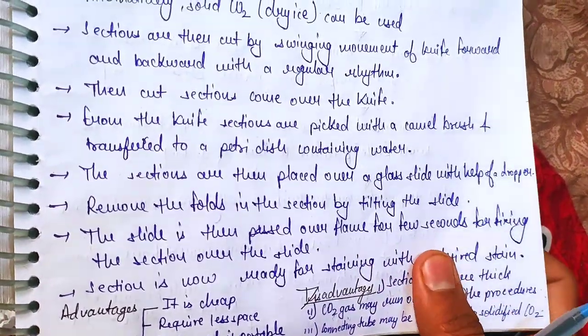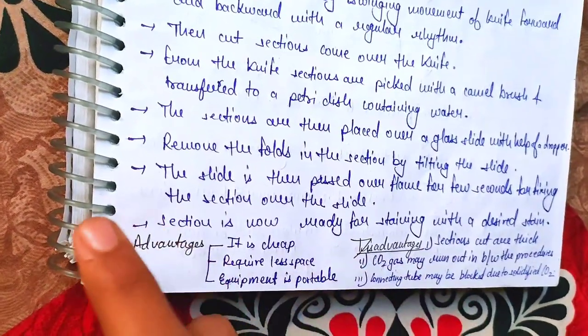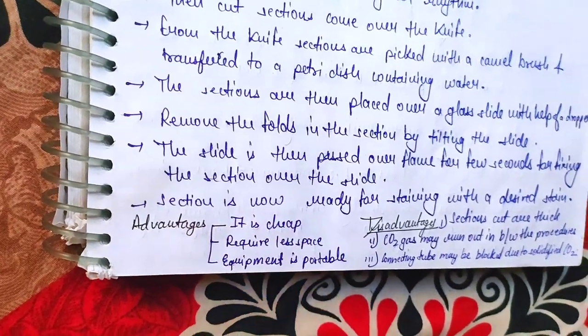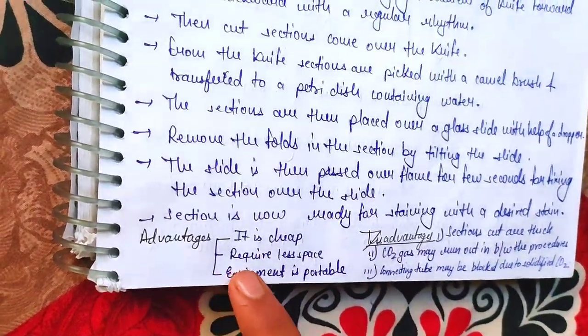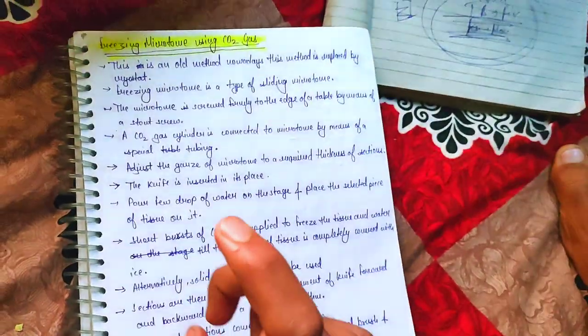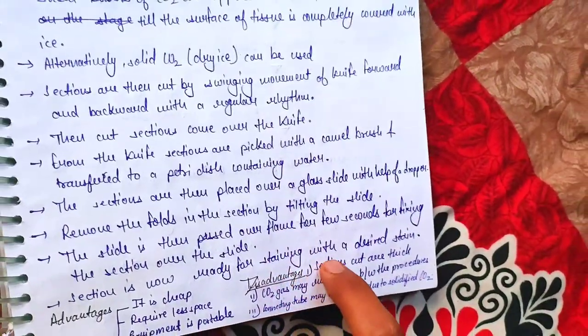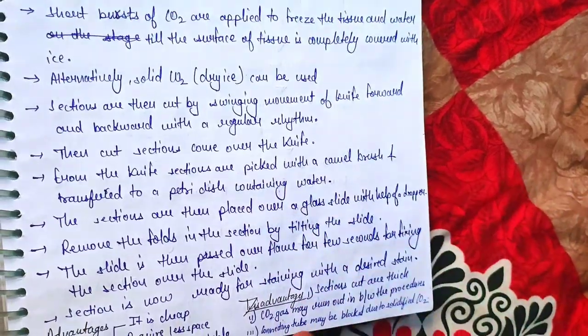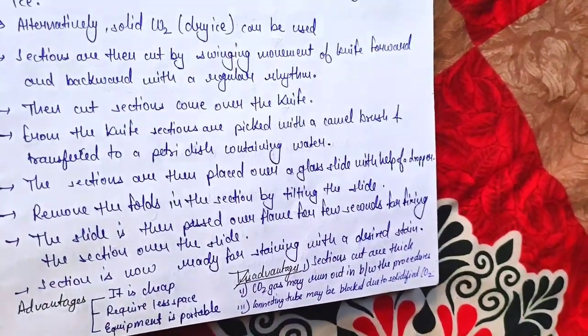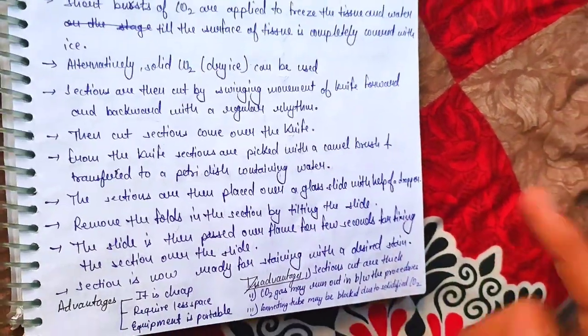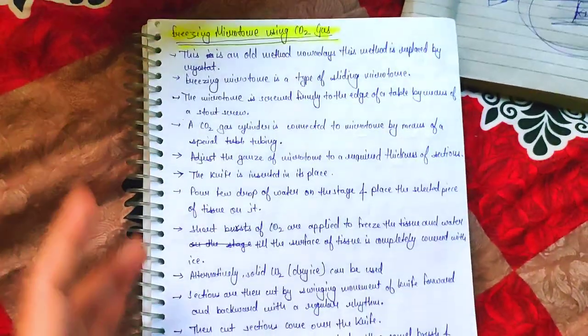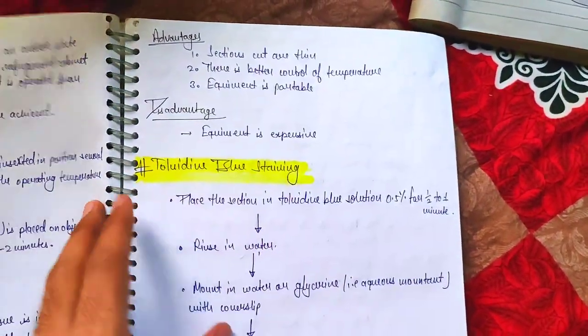The section is now ready for staining with the desired stain. The advantages of this CO2 freezing microtome method are that it is cheap, easy, requires less space, and the equipment is portable — you can take it from one place to another. The disadvantages are that sections tend to be thick, the CO2 gas can run out, and the connecting tube may be blocked by solidification of CO2.